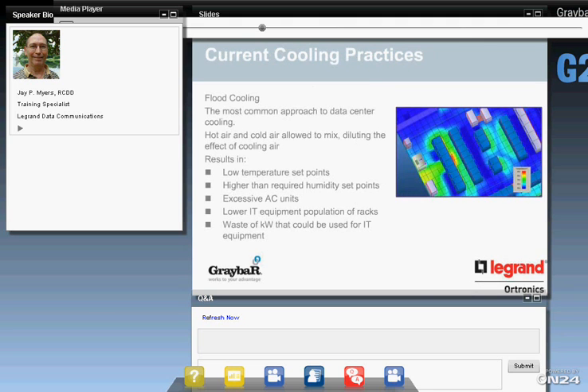Now, how do we take the next step in cooling? So now we've looked at the rack level. Now, how do we look at the entire data center and try to improve cooling here? Most data centers today are still cooled by just flood cooling. Just flood as much cold air as you can get into the room through the raised floor, and hope for the best. What this results in is that the temperature set points are lower than they need to be, because you have to keep the very hottest rack cool enough so everything else gets overcooled.